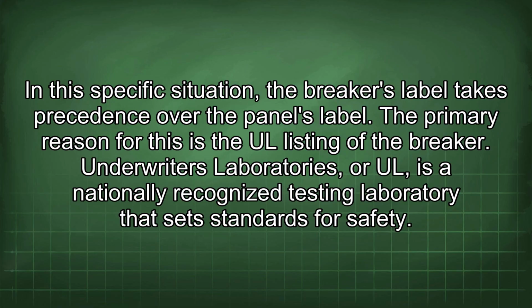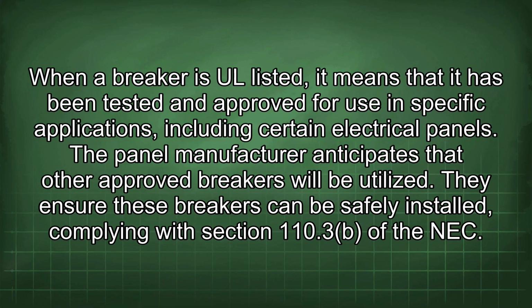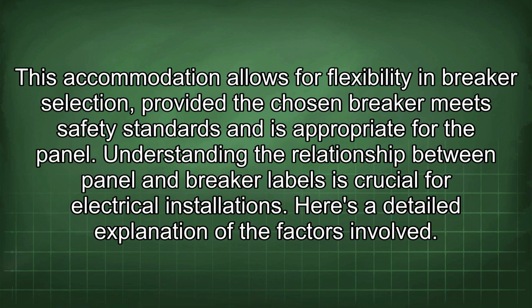Underwriters Laboratories, or UL, is a nationally recognized testing laboratory that sets standards for safety. When a breaker is UL listed, it means that it has been tested and approved for use in specific applications, including certain electrical panels. The panel manufacturer anticipates that other approved breakers will be utilized. They ensure these breakers can be safely installed, complying with Section 110.3 of the NEC. This accommodation allows for flexibility in breaker selection, provided the chosen breaker meets safety standards and is appropriate for the panel. Understanding the relationship between panel and breaker labels is crucial for electrical installations.